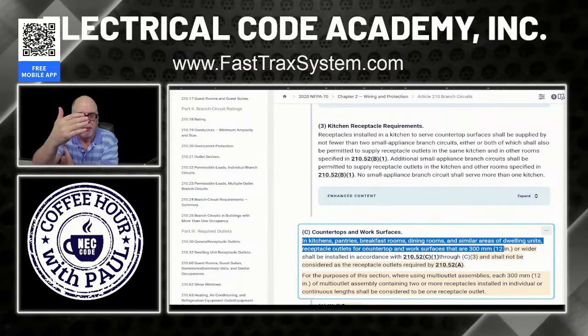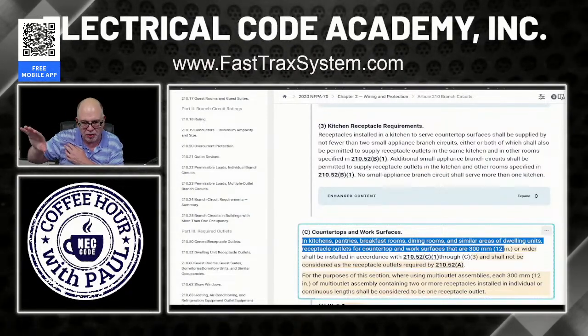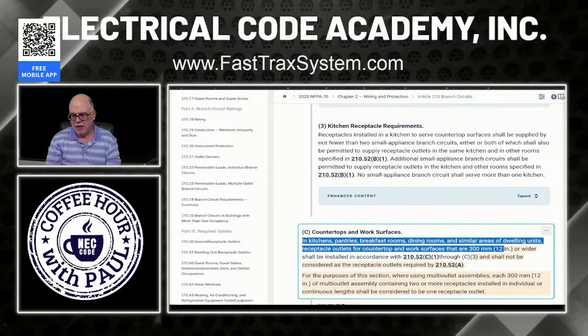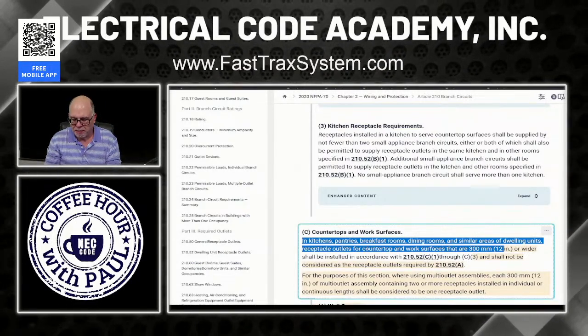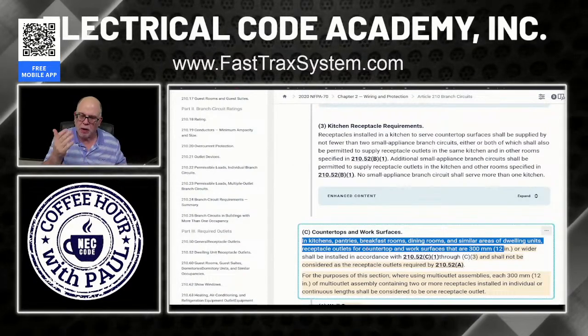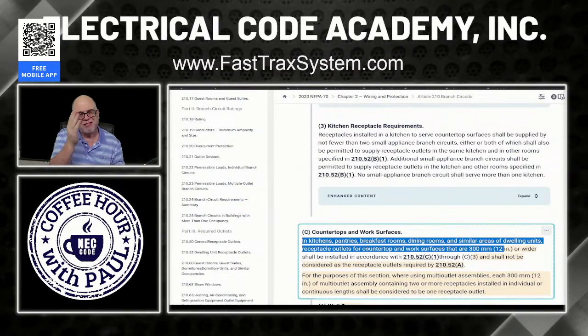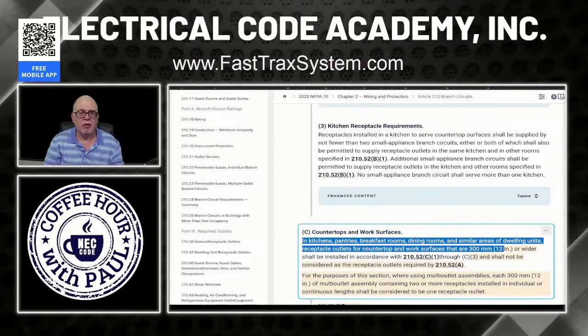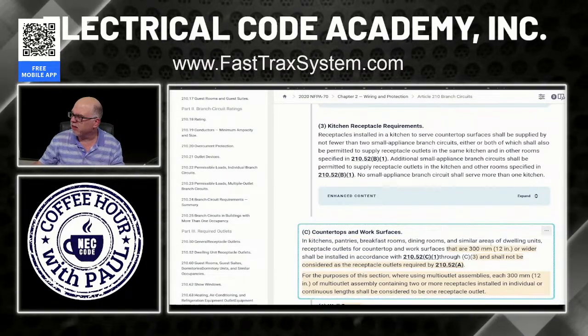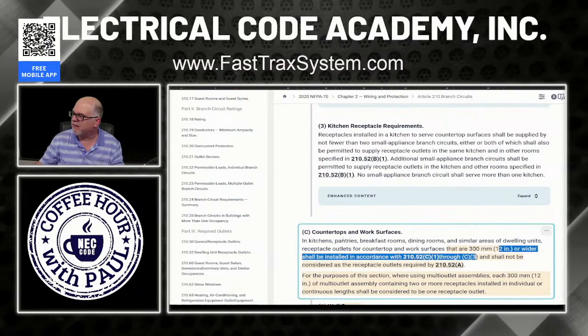It's an interesting question. People say to me, Paul, what if you're wiring, and we'll get back to the counters, and the sink and the cooktop and all that. We'll get to that in a second. But some people say, Paul, what if it's an efficiency apartment and I have a counter with maybe a cooktop or a range in it, and the counter beside it is 18 inches. Would I require a receptacle there? Because remember it says within 24 inches, but this counter is only 18 inches. Do I have to have a receptacle there? And the answer is yes. Based on this right here, 12 inches or wider, shall be installed in accordance with 210.52(C)(1) through (C)(3). It means I've got to have a receptacle there.